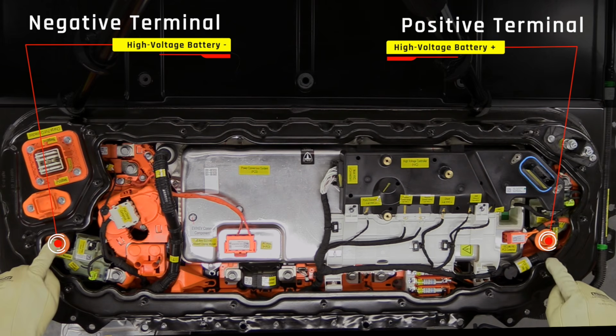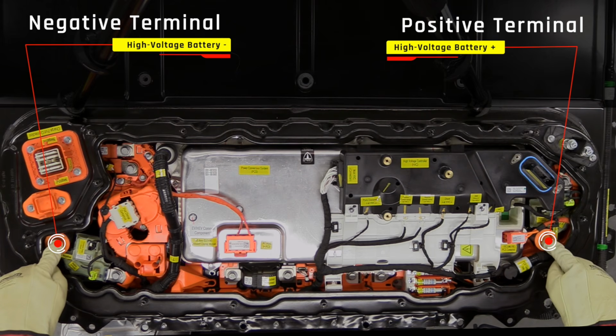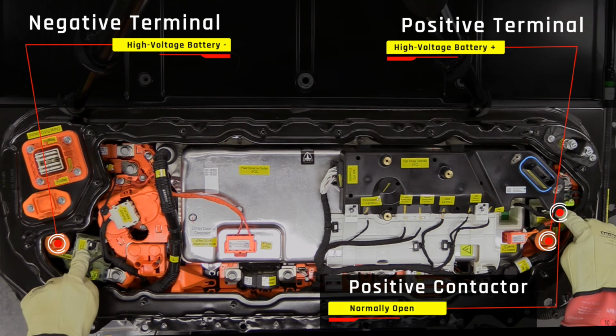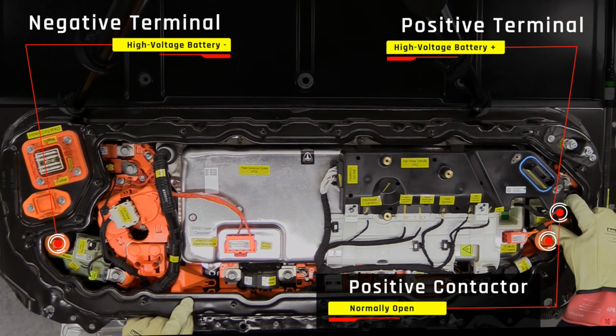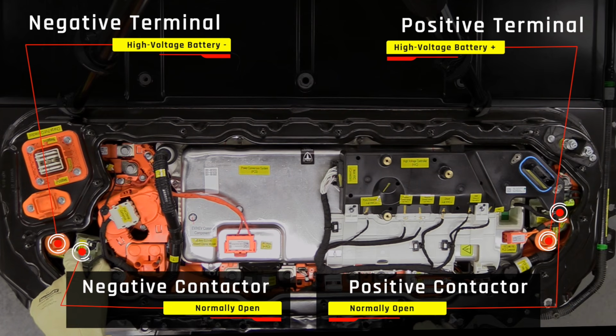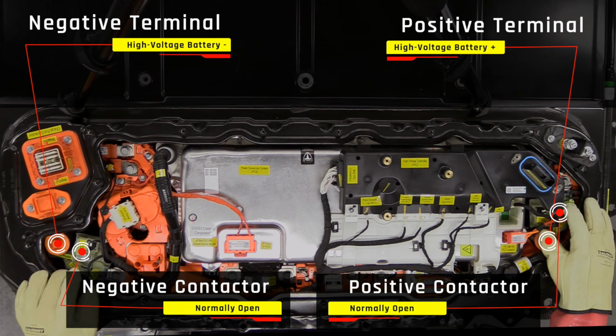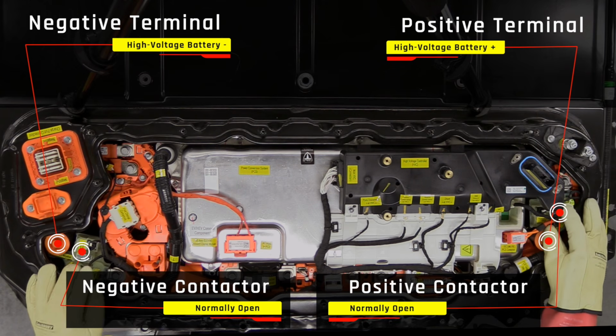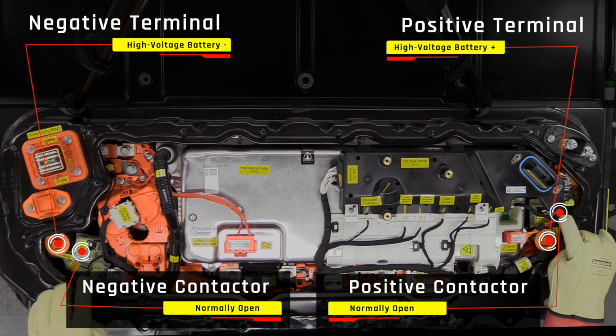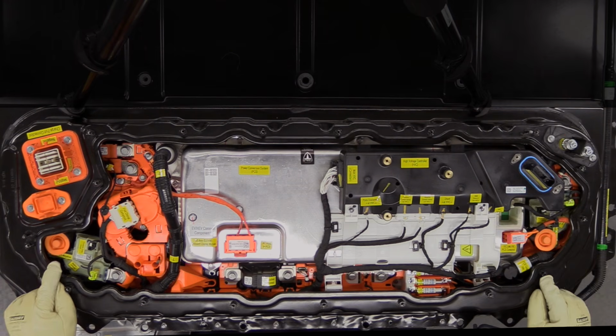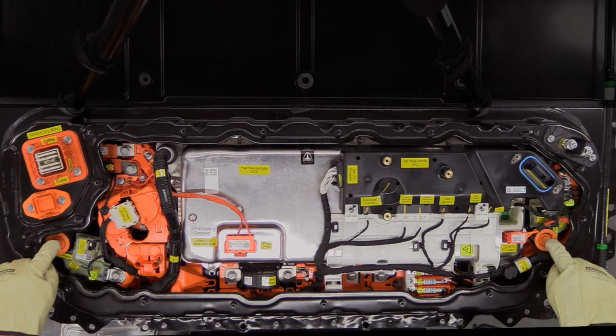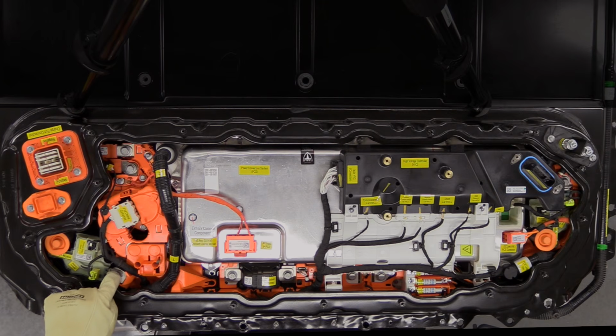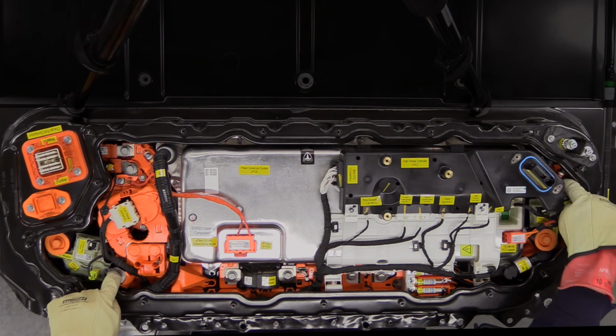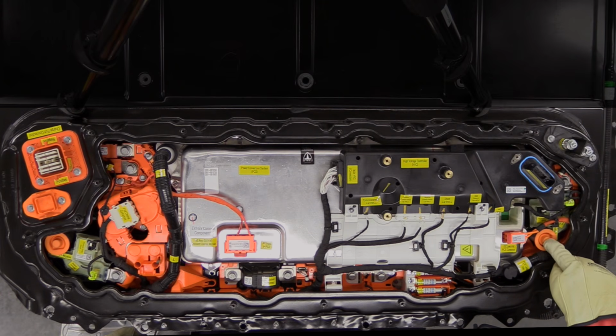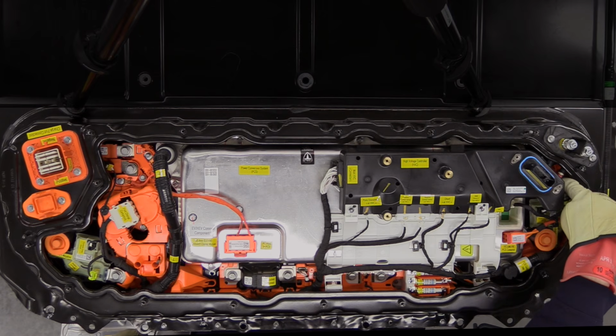Now, these 2 high voltage terminals connect to contactors. So we have a high voltage positive contactor and a negative contactor. And we haven't talked about contactors yet in my training videos, but these contactors are normally open, which means there's no connection from the high voltage terminal to the other side of each contactor. So we have high voltage here, positive, but we do not have it over here.